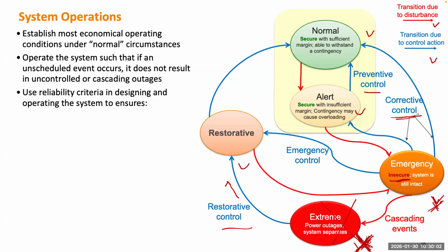The control action is such as, if some device has a low voltage that can damage that device, you need to trip that device. You can open the line and trip a generator. If one generator is operating at very low frequency, there will be a local protection to trip that generator. All the protections or remedial actions are considered corrective control. In terms of terminology, sometimes engineers say protective actions, and some engineers say remedial actions, remedial control actions. Usually protective action means protecting an individual piece of equipment, and remedial control action means protecting one area of the system. It's like a wider area protection. But anyway, both are considered corrective actions. So with corrective actions, there's no waiting. As long as you know the state, you have to act immediately.